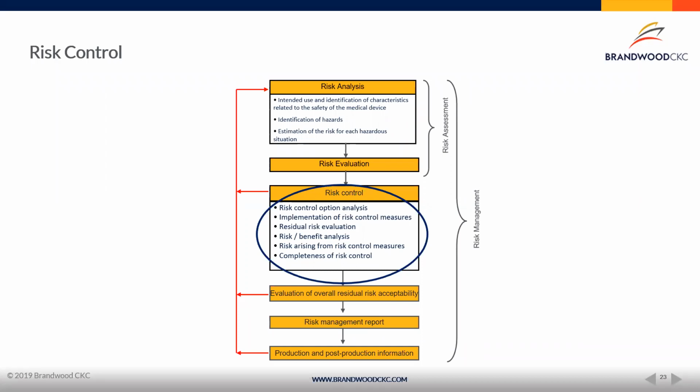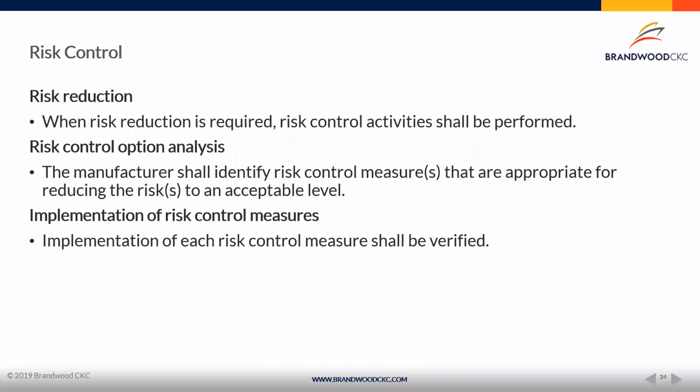And then how complete is the risk control? So have you done everything you can to mitigate or reduce the risk for your device as much as possible? And that analysis needs to be a part of your risk control. So again, when available or when risk reduction is required, risk control activities shall be performed.